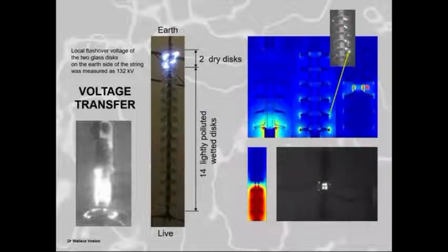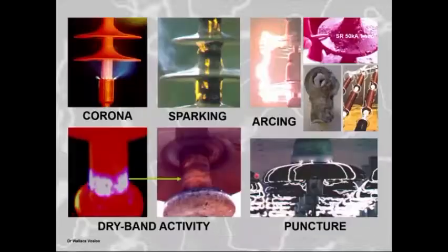And then if we now have a dry band area, which we created in the center, you can see that the voltage potential goes up here and the earth potential comes down, and all the stresses are sitting here in the middle. This here is on an insulator which I had up in one of my test stations, showing exactly that. And you can see the phenomena.